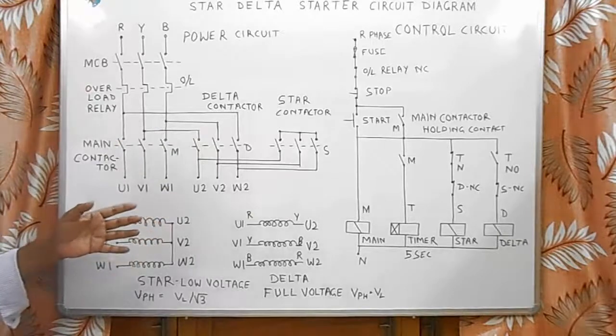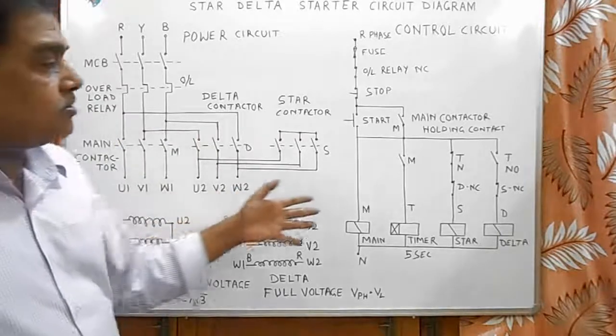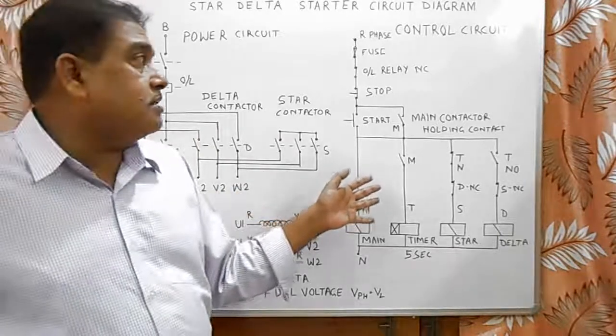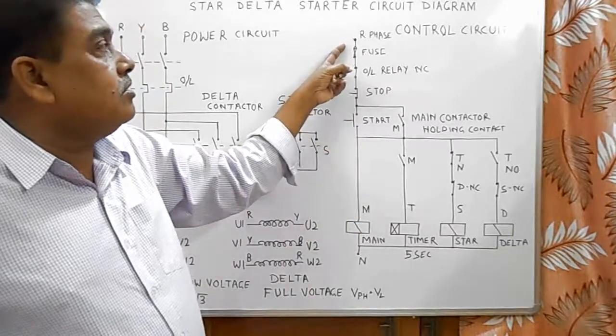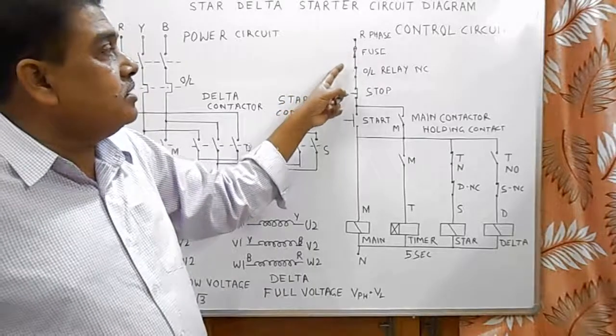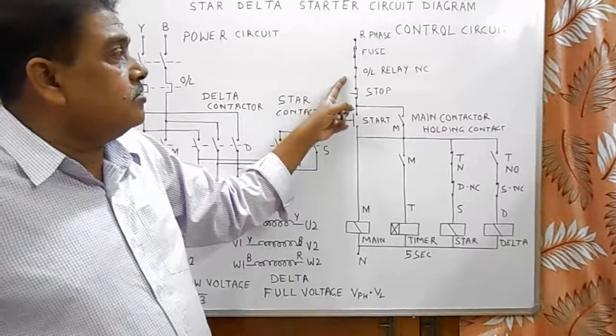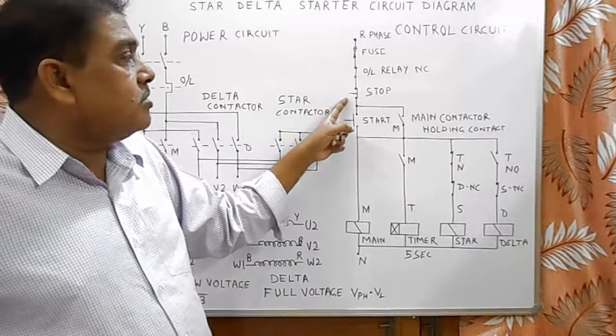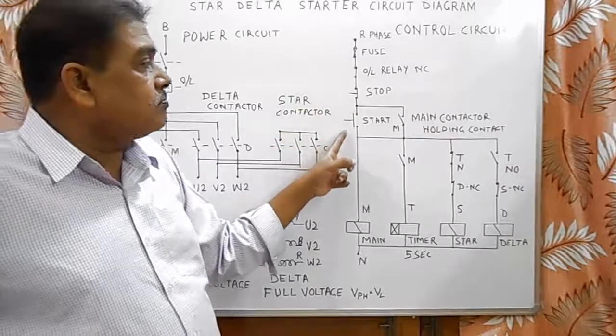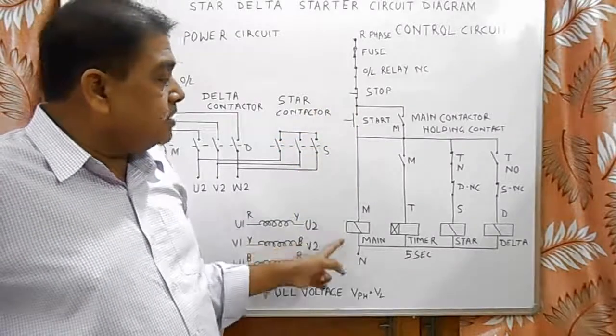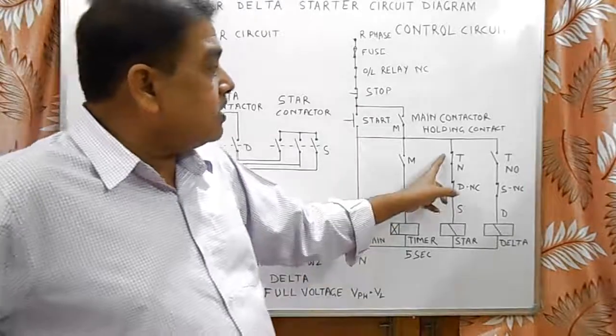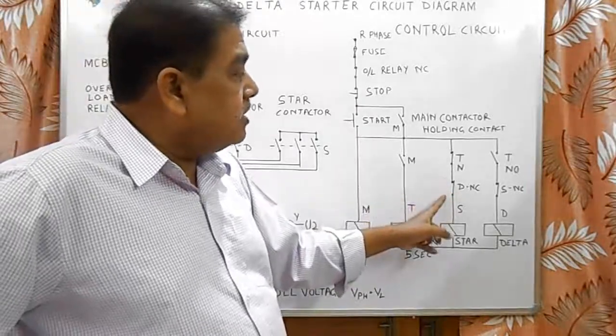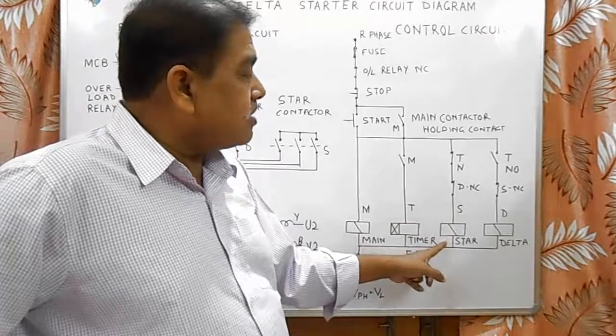For this scheme to work properly, we have a control circuit. In this control circuit, R phase supply is taken for control. It goes to control fuses and from there to overload relay and then to stop button. As soon as we push start button, main contactor picks up and with the help of timer NC contactor and delta NC contactor, star contactor picks up.